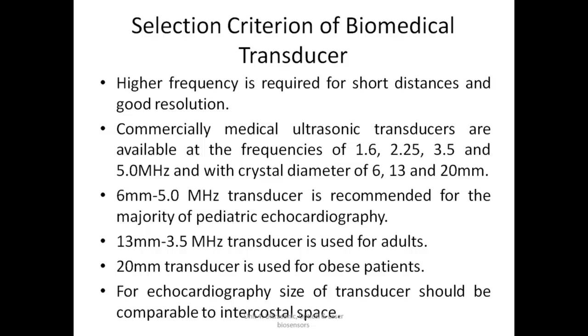The commercially available medical ultrasonic transducers come in frequencies of 1.6, 2.25, 3.5 and 5 megahertz, and with crystal diameters of 6, 13 and 20 millimeters. These are the most commonly used commercially available medical ultrasonic sensors. A 6 millimeter, 5 megahertz transducer is recommended for the majority of pediatric echocardiography. That means if you have to use it for a small child, first the size has to be very small, so we use the smallest diameter, 6 millimeters. And since for short distances we use high frequency, 5 megahertz is used for small child echocardiography.